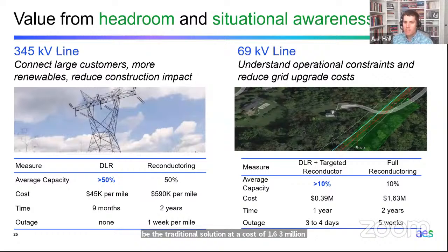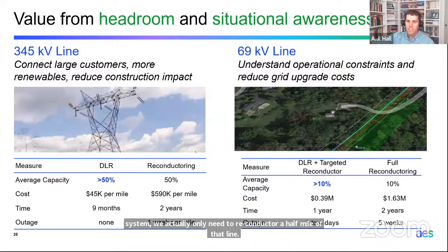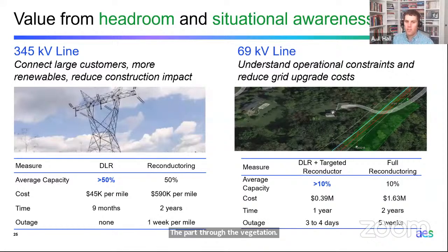However, now that we have dynamic line rating on the system, we actually only need to reconductor a half mile of that line, the part through the vegetation. So currently our system planners are looking at this project, but that would only cost about $400,000 and take less than a week outage to complete.